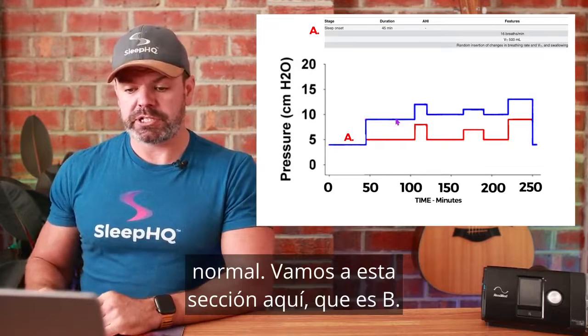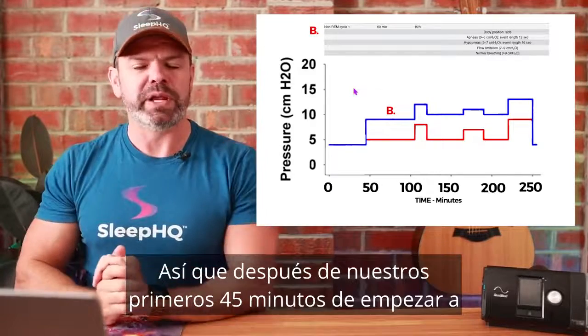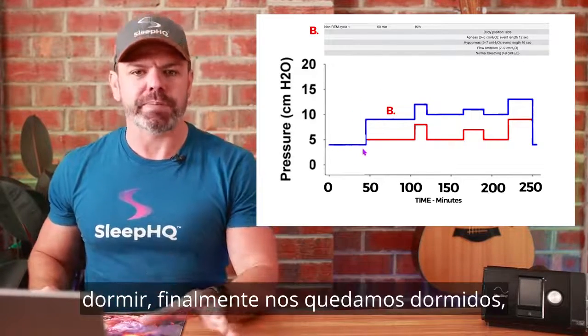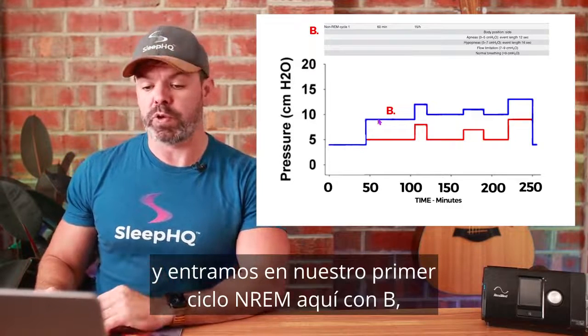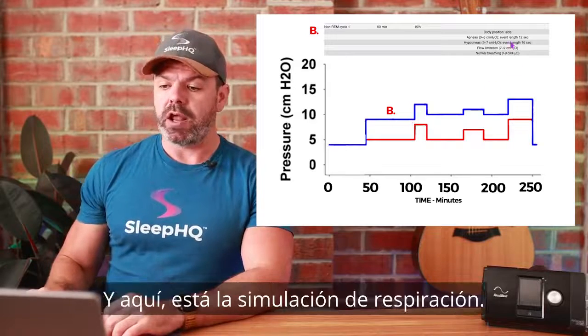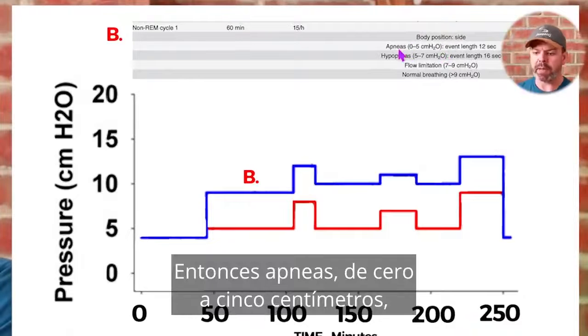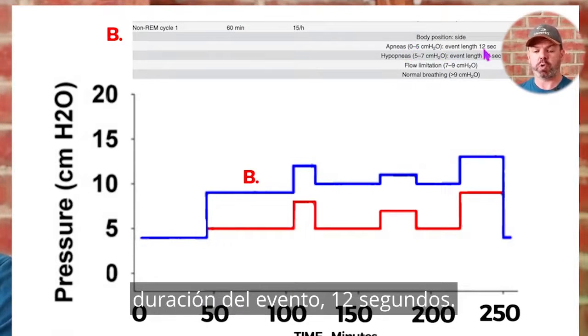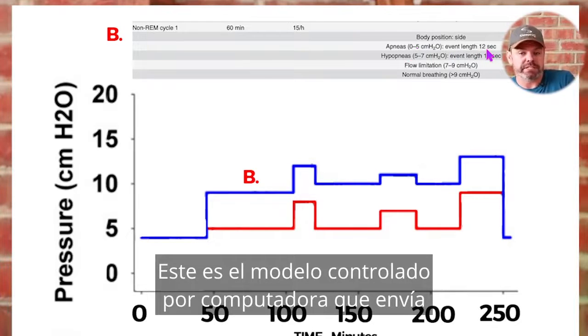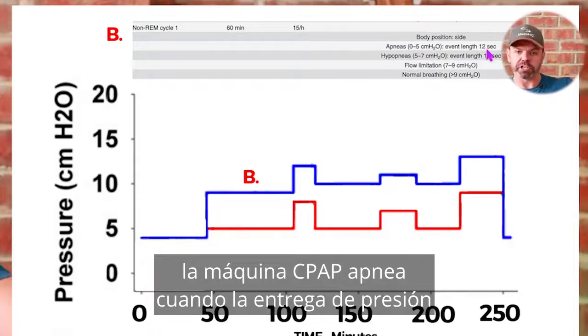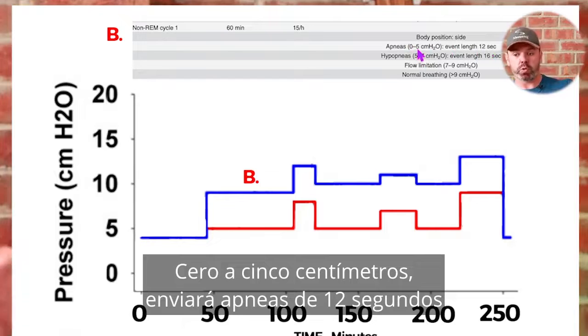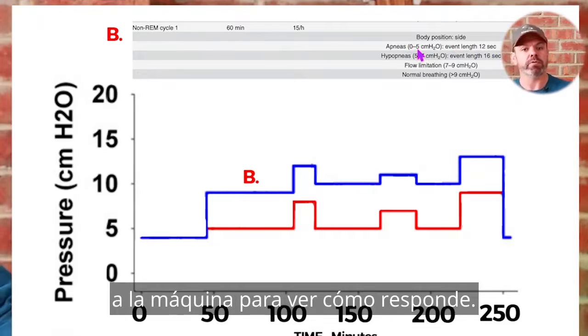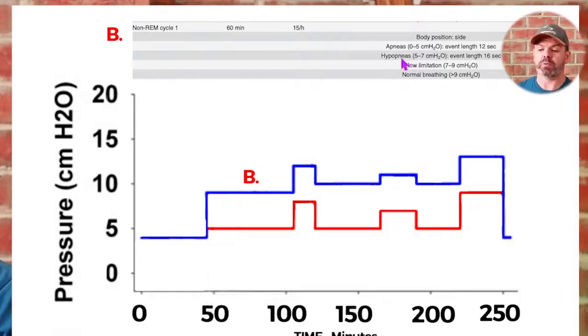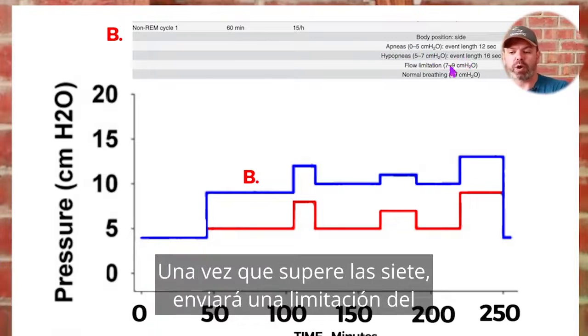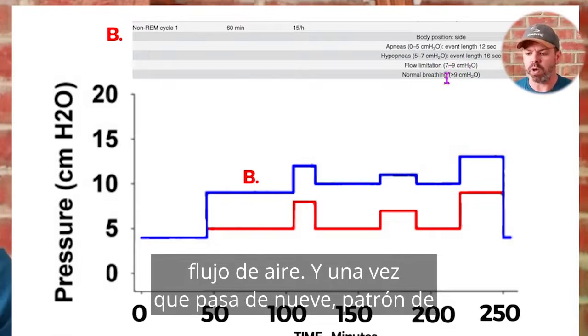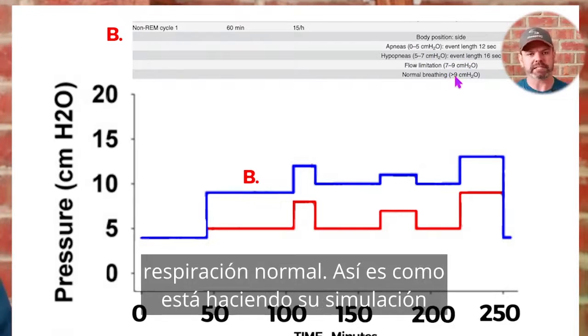Let's go to this section here, which is B. So after our first 45 minutes of sleep onset, we finally drift off to sleep and we enter our first NREM cycle here with B, and it runs for 60 minutes. And over here is the breathing simulation. So apneas 0 to 5 centimeters, event length 12 seconds. So this is the computer-driven model sending the CPAP machine apneas when the pressure delivery is below 5, yeah? 0 to 5 centimeters, it will send 12-second apneas to the machine to see how it responds. Once the machine goes above 5, it will then send hypopneas, 16 seconds in length. Once it goes above 7, it will send airflow limitation. And once it goes above 9, normal breathing pattern. That's how it's doing its simulation, yeah?